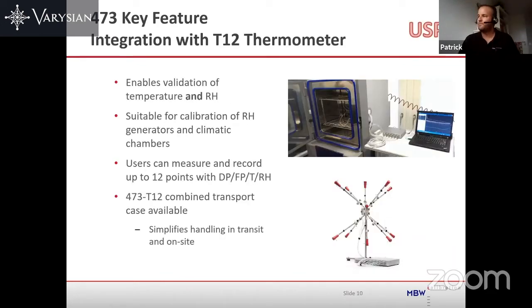A separate and second piece of equipment that we offer is a T12 thermometer. You see it in the top picture. You can see the T12. It's that gray box with many white cables coming out of it, connected to the climate chamber. At the bottom, you see it also working with the spider. The spider is basically nothing more than a fancy way of holding the 12 probes within the climate chamber to make sure you can measure throughout and evenly the chamber.